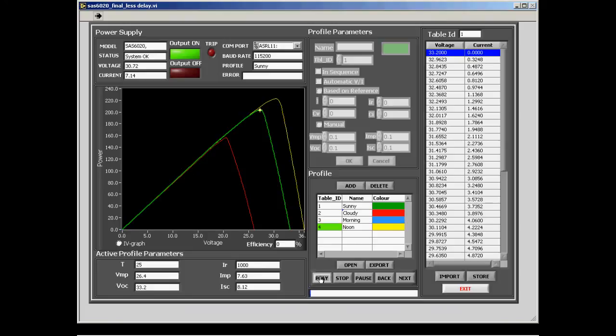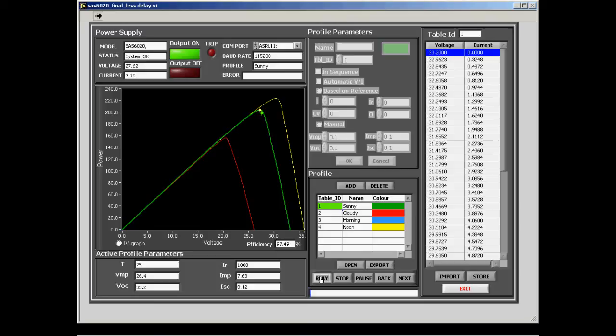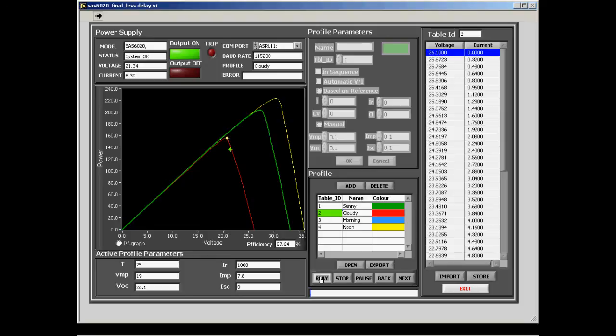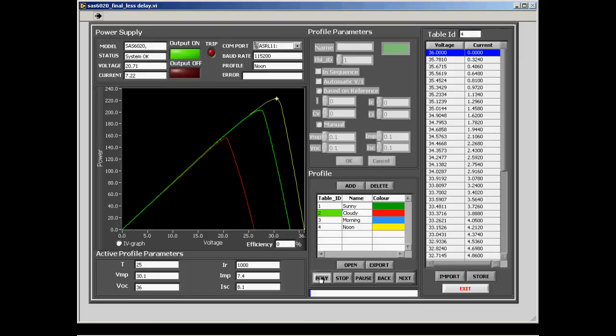Now we will demonstrate the sequence mode. The user has the flexibility to run multiple IV curves to simulate the radiation intensity and temperature changes throughout the day. It helps the user to do the maximum peak power tracking test under diverse environmental conditions. High speed transfer of curves makes the profile transition seamless to the user. As you see the operating point stays at the maximum point for different curves and the micro converter is able to track the maximum power point.